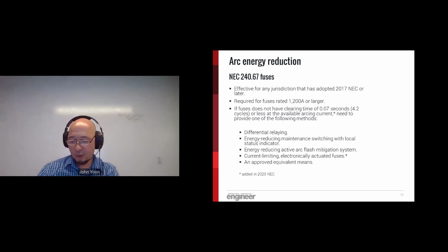So the energy released by an arc flash is characterized by the equation I squared T, with the variables being current and time. So based on that equation, limiting the available current can have a significant impact on the amount of energy released. However, for many installations, you can't adequately serve your load unless you have that high capacity electrical distribution equipment, so you're stuck. If you can't limit your fault current because you have really big equipment, you have to address the other component of I squared T, basically the time component. You have to clear the fault as quickly as possible.